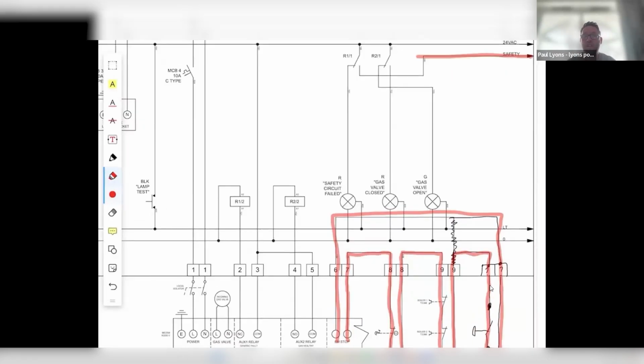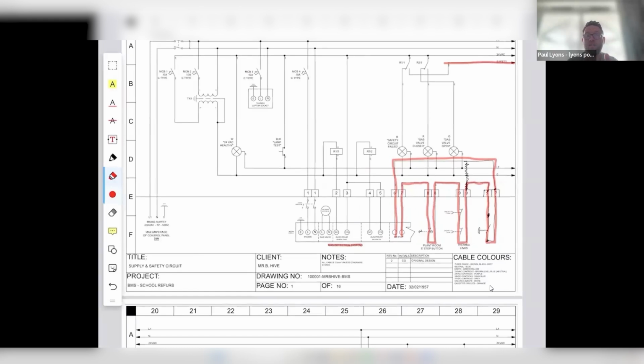Talking from an industrial process, it's different on a safety circuit. Instead of just having one channel there, that could go faulty and you might not be able to trigger the safety when you need it. So someone can get injured, or something could blow up, things could go to shit basically. So you'll have different layers, like another cable running alongside the single one, and I think they go up to quad channel safety circuits. It's about making sure that if something does fail, there's another layer of protection there to cover your arse, to stop anything going awry.